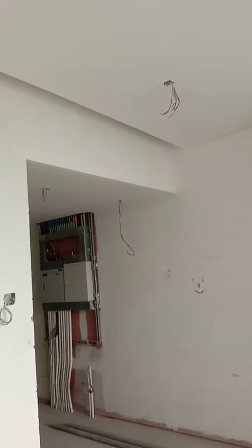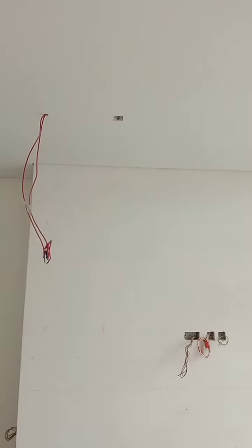But I left one point: before we proceed with the installation of the devices or the final fix, we have to make sure that we carry out certain testing, which is the dead test at this level. Since the installation is dead, there is no power supplied to our panels or our distribution board. So we have to conduct continuity tests as well as insulation resistance tests. Get the values. The values should be okay and approved by the consultant before we can proceed to the next level, which will be the final fix or the third fix, which is very important.